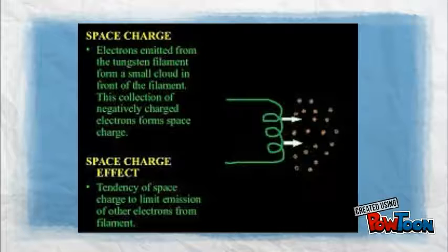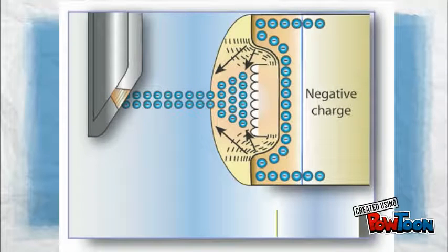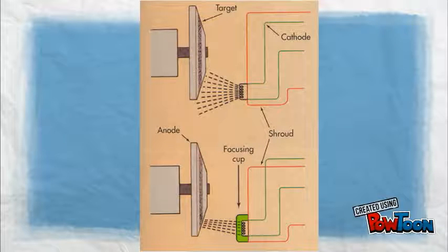This is where the focusing cup comes into play. The focusing cup, which is made of molybdenum, is a shallow depression in the cathode that houses the filament. The filament emits electrons, all of which have a negative charge. Since negative repels negative, the electrons that have been emitted have a tendency to diverge. As this is counterproductive in x-ray tubes, the focusing cup is a negatively charged housing that encourages the electrons to stay together. Essentially, the force that causes the electrons to repel each other is overpowered by the repulsive force of the focusing cup, and the electrons tend to converge rather than diverge.